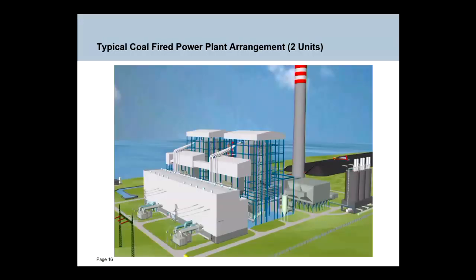Okay, this is then a diagrammatic of a typical 2-unit power station. So what do we have? Coal stack, the coal reserve here. This is the stack from the boilers. Gas cleaning plant, boilers where the coal is burnt and steam is produced. Turbine house, which has the turbine generators in it. Transformers which take the electricity at, say, 20,000 volts from the generators, step it up to, say, 500,000 volts for the transmission system, and then transmission lines to take the power away. Most power stations look like this, 2 units or 4 units or 6 units, with the units being independent of each other.